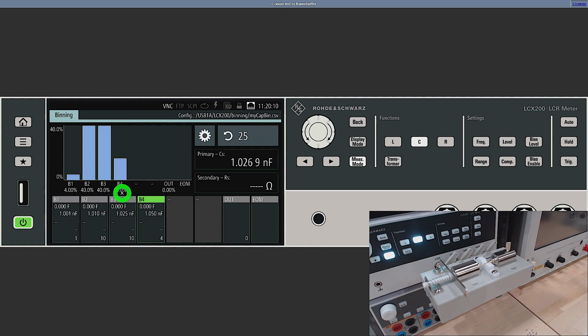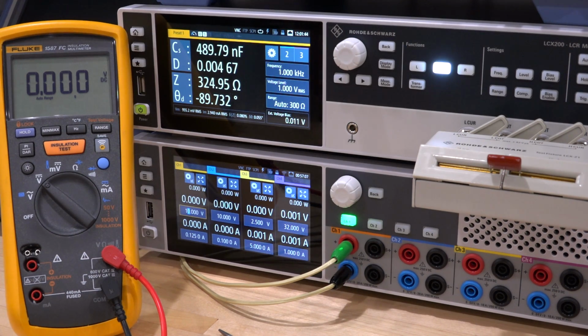Now keep in mind that this is plus and minus, so if you want to define individual absolute values, I think you also can, but this way anything below and above that fits within 2.5% falls in the same bin. And there were actually no rejects in this case. So this is pretty good. These capacitors are expected to behave very well, but being able to do this binning automatically built into the software can be quite helpful. And let's quickly try out the external bias voltage capability of the LCX here.